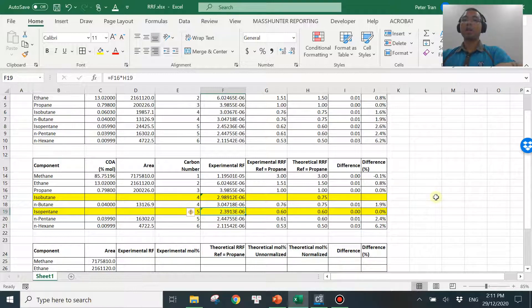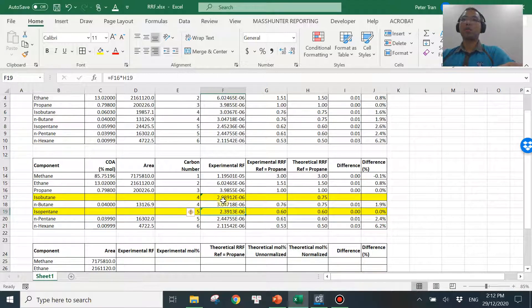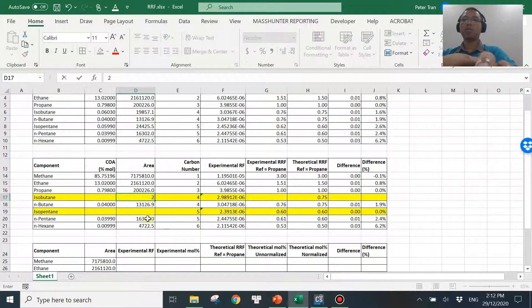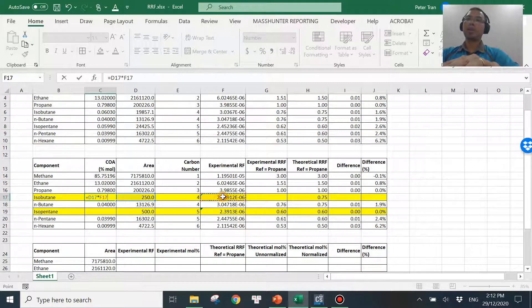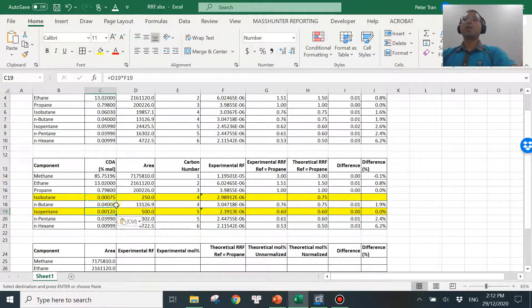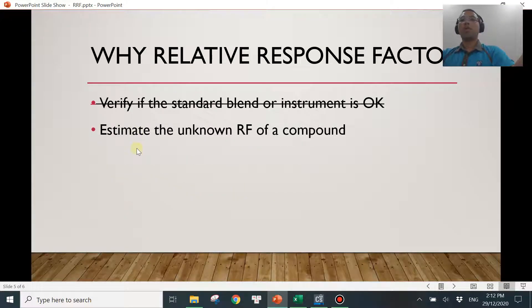In fact, this is a very common way in a lot of ASTM, UOP, and GPA methods, and many manufacturers have been doing it like this. So you should be good to use this technique to perform this RF calculation. Once you know that RF, it's very simple — you'll be able to calculate the concentration in your sample when you run it. You get some area counts, say 250 or 500 for example, and the concentration is just the area counts times the RF. That's how you end up with the concentration very easily.